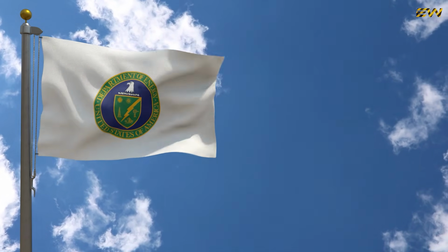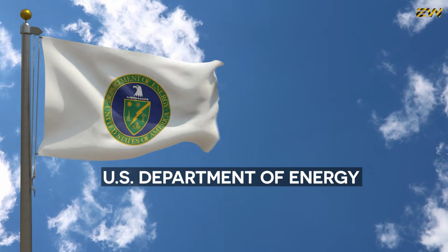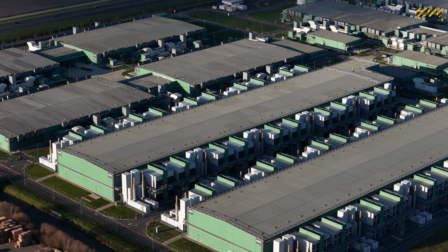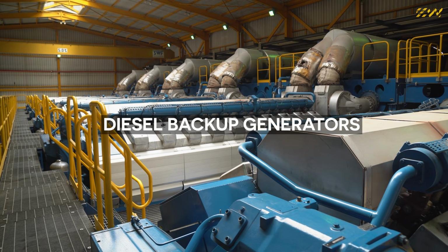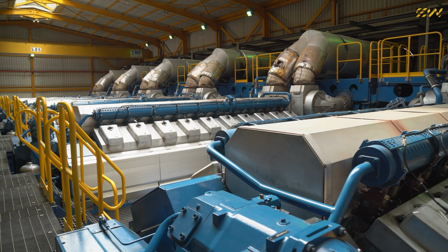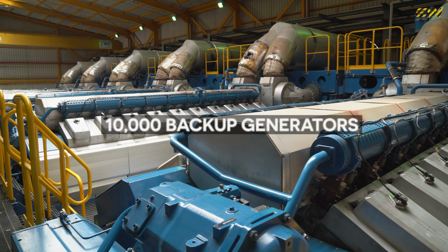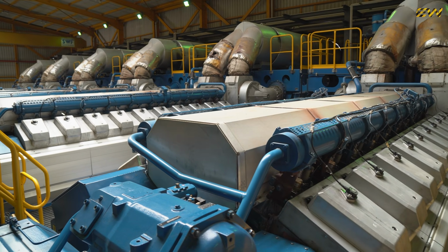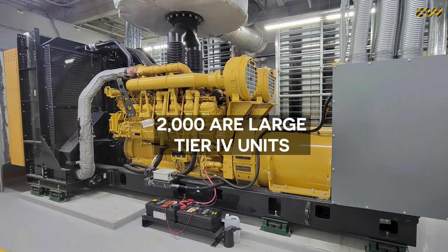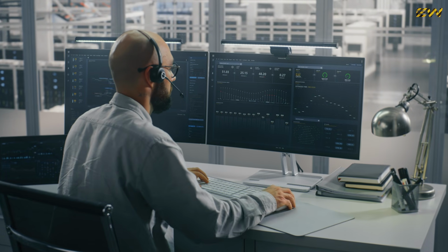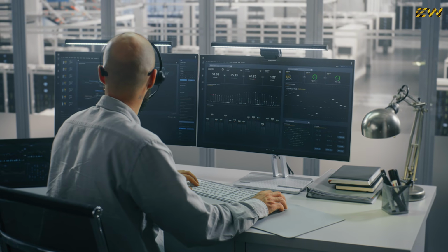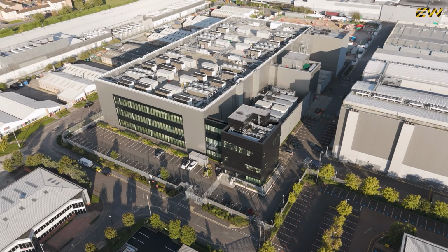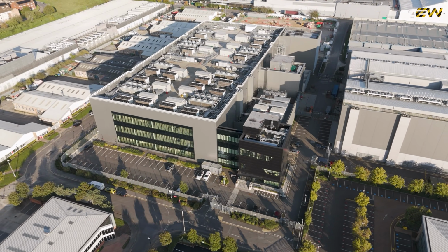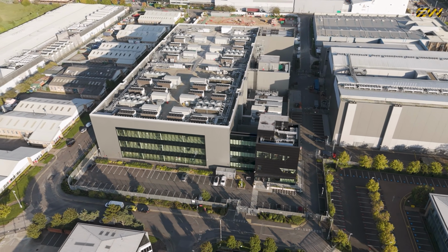And when extreme weather hits, in January 2026, the US Department of Energy allowed some Virginia data centers to operate solely on diesel backup generators to preserve grid capacity. There are an estimated 10,000 backup generators in Virginia. About 2,000 are large Tier 4 units. During peak operation, emissions can rival small power plants. The infrastructure simply can't expand as fast as digital demand.